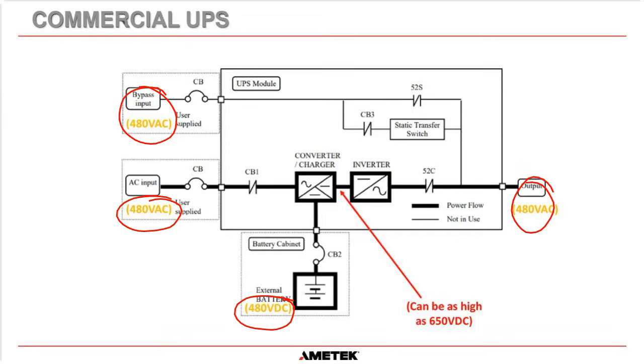And what a lot of people get confused about, especially with a commercial UPS, is yes, we do have a high DC battery. It's at 480 volts. But the DC bus between the charger and the inverter actually gets boosted up, and it can be as high as 650 volts DC. Okay. They use high voltages inside commercial UPSs usually. And there's a good reason for that, and that is because the higher the voltage, the lower the current. So if you're going to buy components or wiring for inside a UPS, if you can save money by increasing the voltage, which therefore reduces the current, you can use less copper. You can use lower rated IGBTs and SCRs inside your system, and it just makes it easier to build a cheaper system. So that is why most commercial UPSs use a high DC bus.